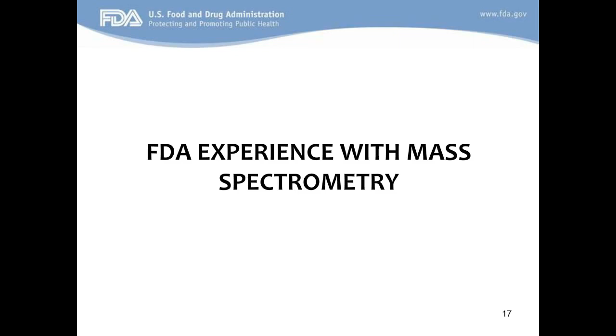To start with, the mass spectrometer, the instrumentation itself, and this is also true of high-performance liquid chromatography, or HPLCs, the instruments themselves are what's called Class 1 exempt, which means they're low-risk devices that do not require a formal submission to the FDA, but they do have to be produced under good manufacturing practice. The manufacturers of the HPLC or the mass spec must be registered and listed, and there is a database of companies registered and listed to market HPLC and mass spectrometers for clinical use, publicly available on the FDA website. The important thing to keep in mind, though, is that even though the mass spectrometer itself is Class 1 exempt, when the assay is added onto the instrument, that whole system, the mass spec plus the assay, becomes classified as the risk of the assay itself.